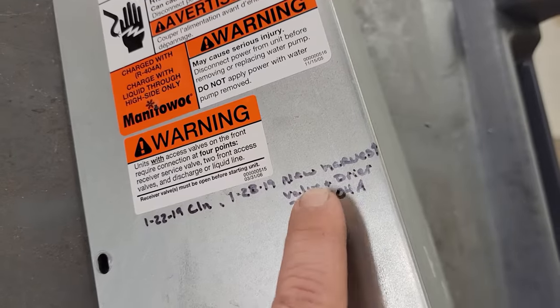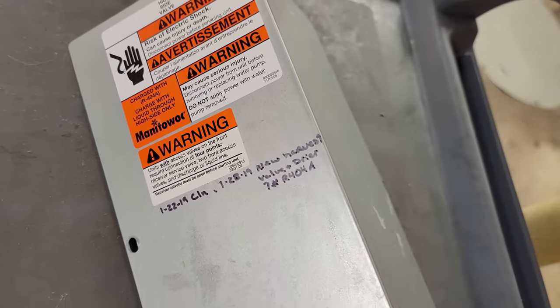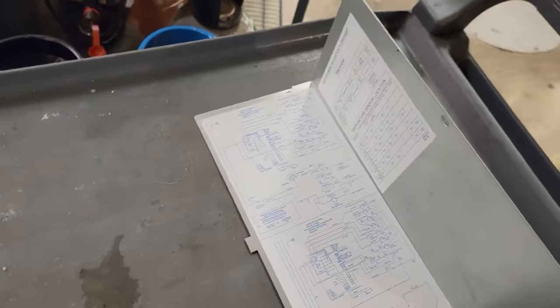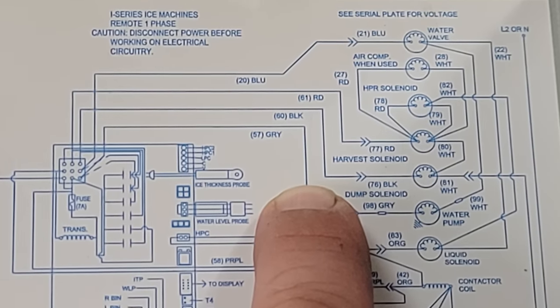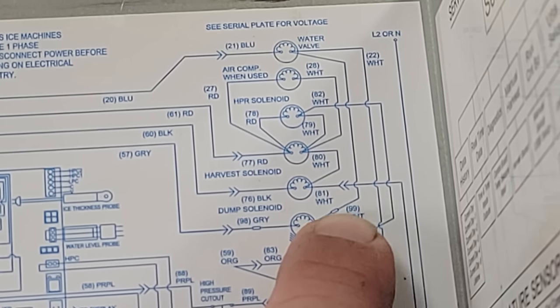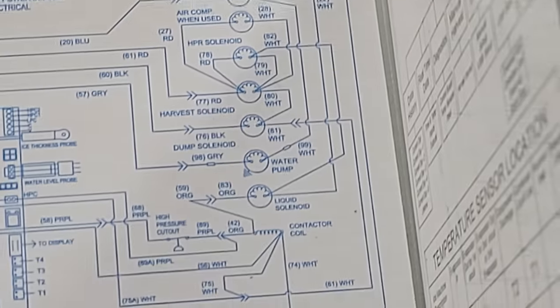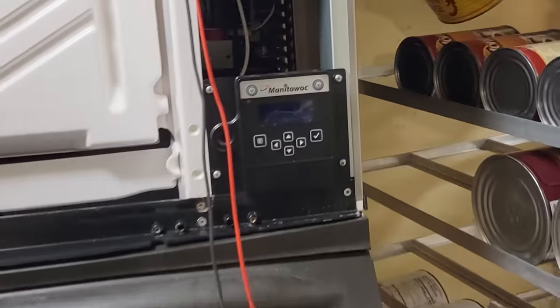I put a new harvest valve and dryer in this thing back in January 2019, so here we are in March of 2023 — this lasted almost four years. About time to throw it away, I suspect, with the way things are built today. Looks like the gray wire going up to the water valve. Let's go check and see if we can find some grounded motors.